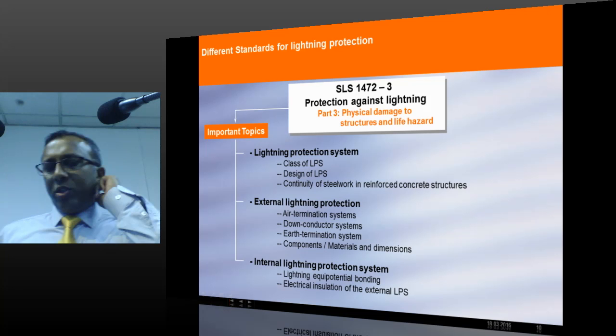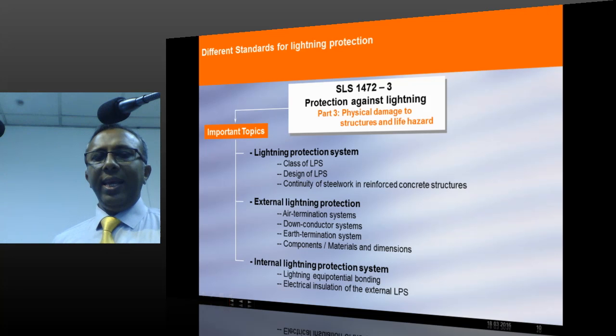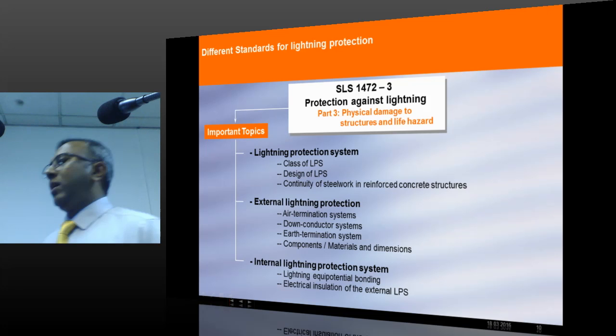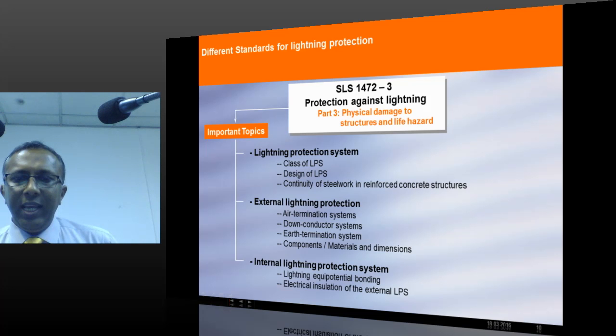The standard also talks about lightning equipotential bonding and electrical insulation of the external lightning protection system. Imagine you have a building and at the top of the building you have an air terminal, let's say maybe several air terminals, and there is a chiller, say an air conditioner chiller. Generally what we do is we put a rod maybe a little bit away and then calculate the angle, and if the angle is sufficient to protect against a direct lightning strike, we believe that okay, now the chiller is protected. This is only one part of protection. The second part is how much electrical insulation, what is the distance required to avoid a flashover from your rod to the chiller.